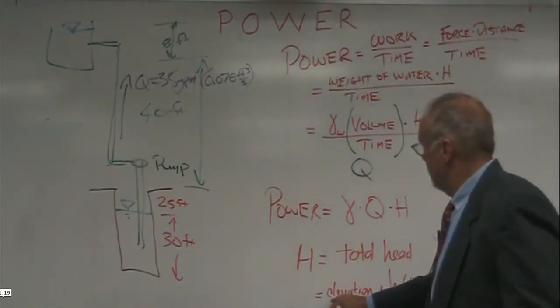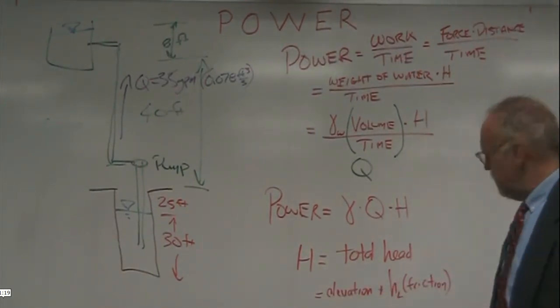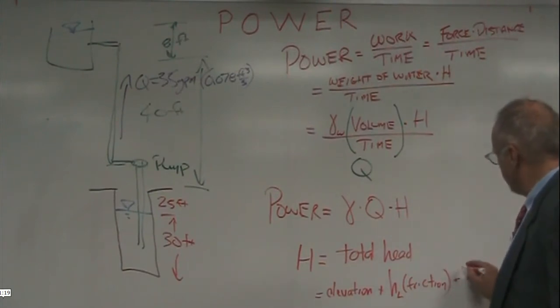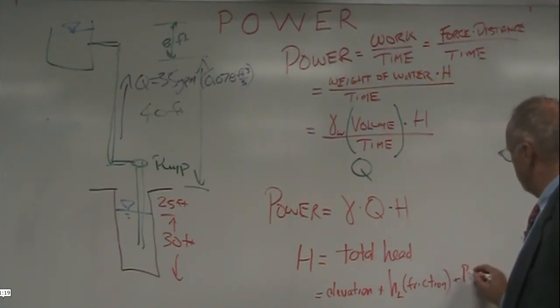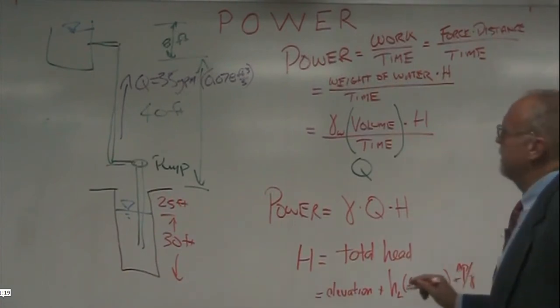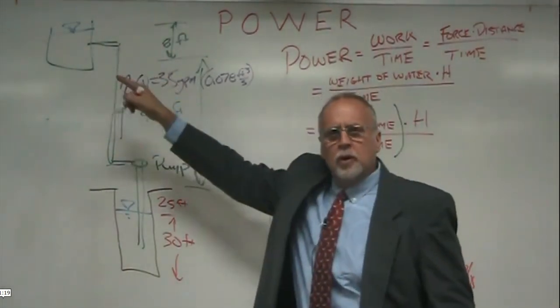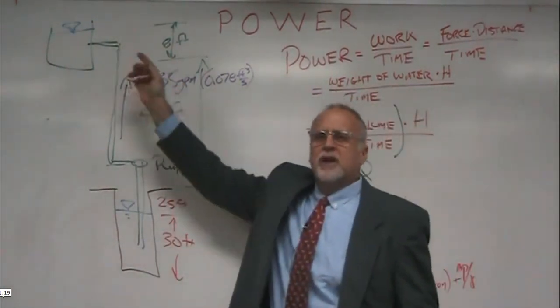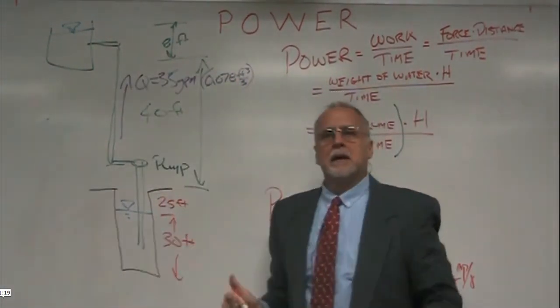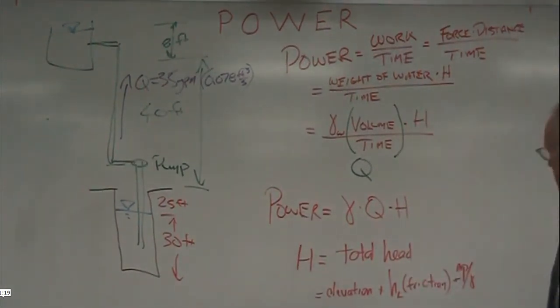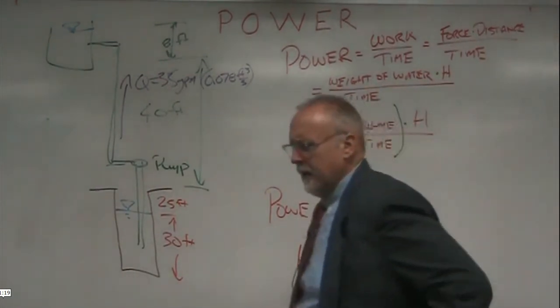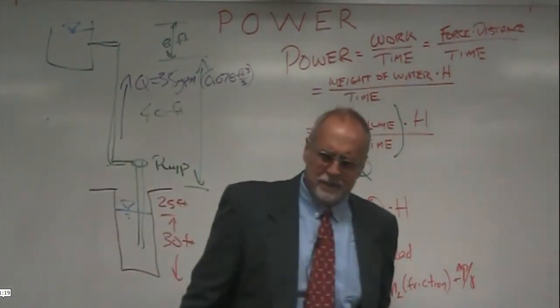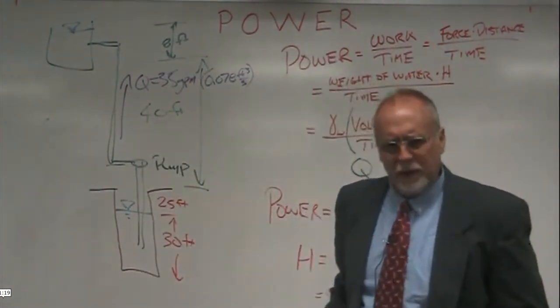That's it. And maybe in some cases, pressure. If we're raising it up to a sealed storage tank, this is an open storage tank. It's open to the sky. But if we had pressure, we'd have to add that pressure to it. What about velocity head? Velocity head in most cases is insignificant. I don't care about velocity head.